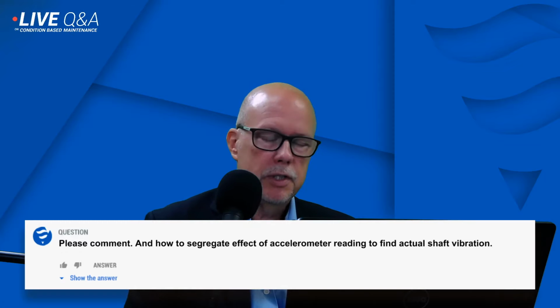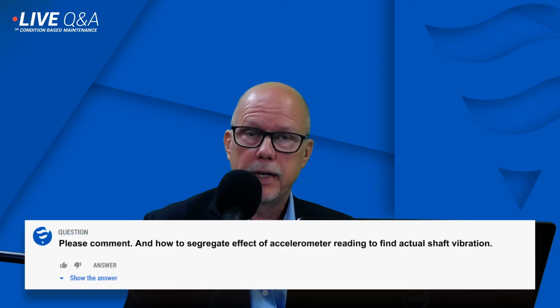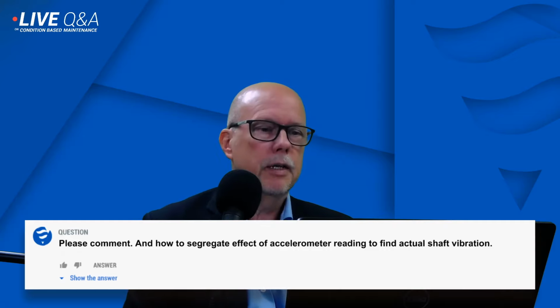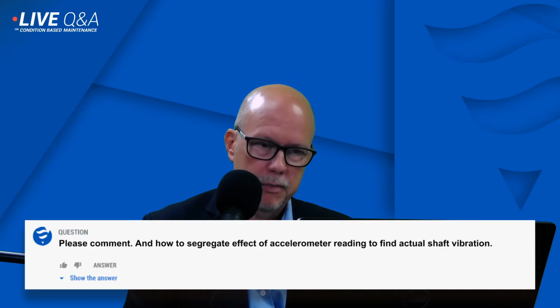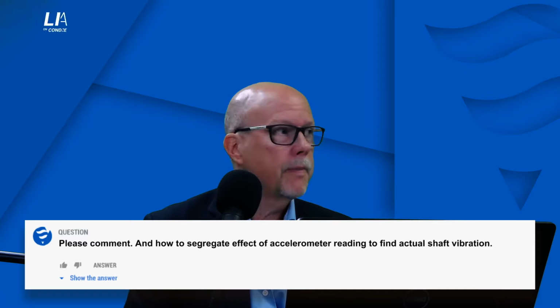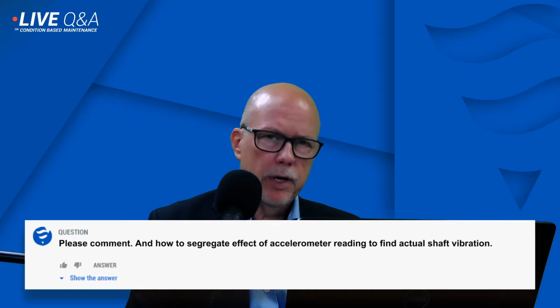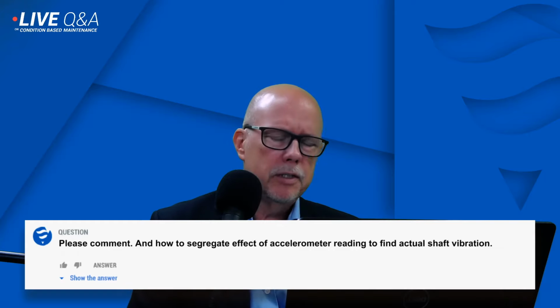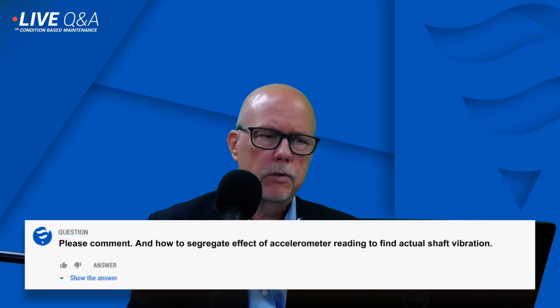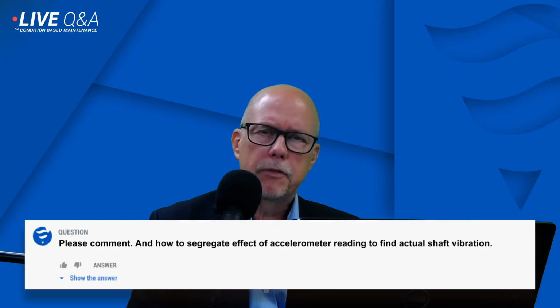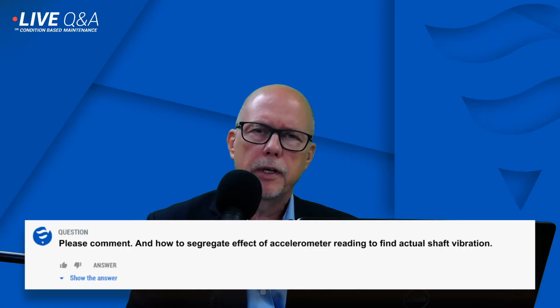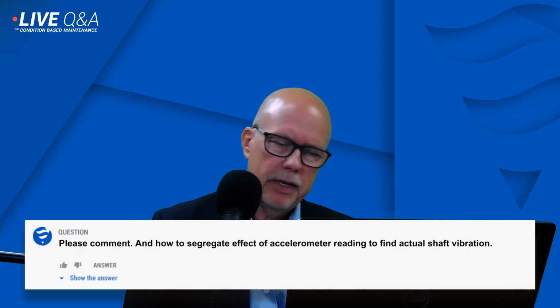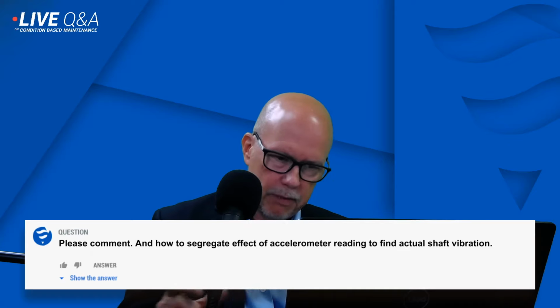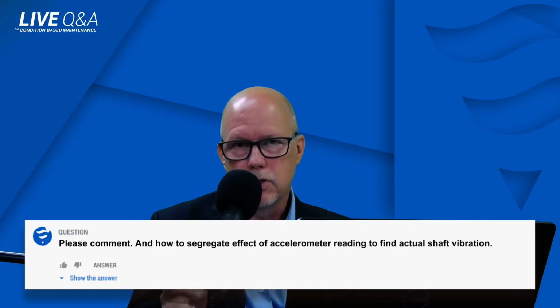in combination to see, first of all, is the bearing housing vibrating a lot, and if so, is it working symmetrically with the shaft or not. We do that also for core and frame structural integrity. In some cases, you will monitor the acceleration of the core and you'll see a certain amount of vibration. And you look at the frame and you see similar amounts of vibration. Usually you see a little more. But if you look at the phase, you find out that they're not necessarily working in unison. There's a time lapse difference between them, telling you that there's some stator core looseness.